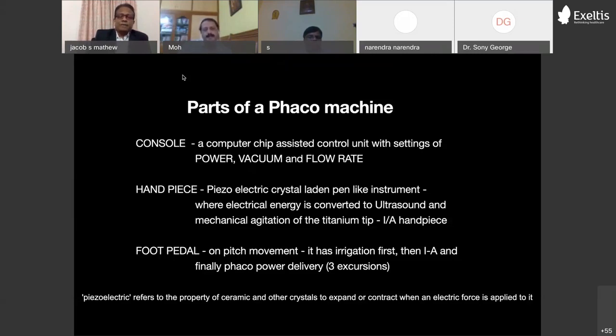The phaco handpiece has three ports at the back. One is where the machine passes its energy into it, to convert the electrical energy into ultrasound mechanical energy. One port takes out the water, it aspirates the water, and the other one causes the irrigation to come in. So the irrigation goes in, and the irrigation fluid comes out from the sleeve through two side ports, around the phaco tip, which is a titanium tip.